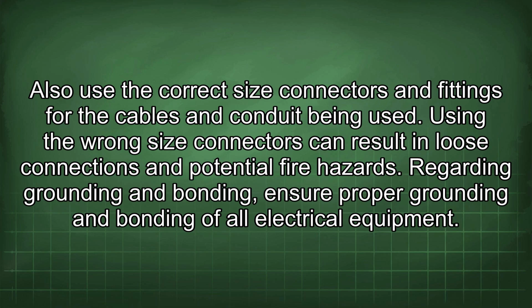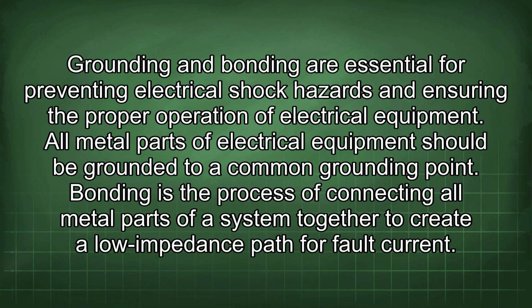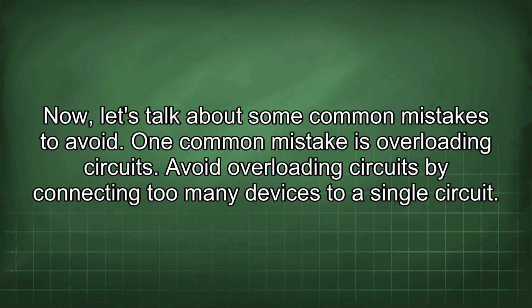Regarding grounding and bonding, ensure proper grounding and bonding of all electrical equipment. Grounding and bonding are essential for preventing electrical shock hazards and ensuring the proper operation of electrical equipment. All metal parts of electrical equipment should be grounded to a common grounding point. Bonding is the process of connecting all metal parts of a system together to create a low impedance path for fault current. Now let's talk about some common mistakes to avoid.